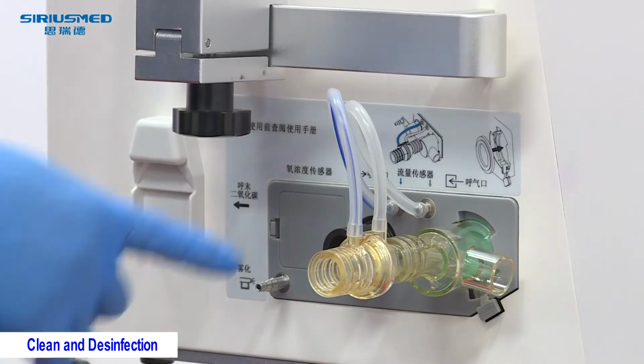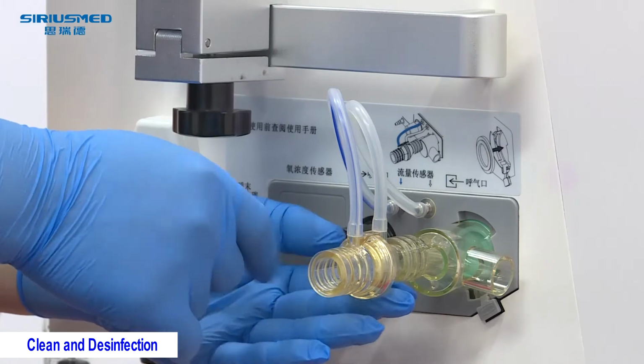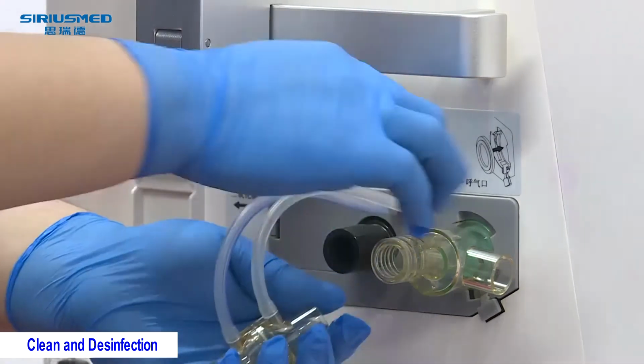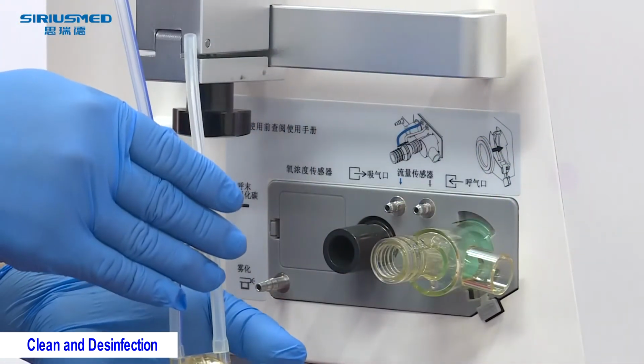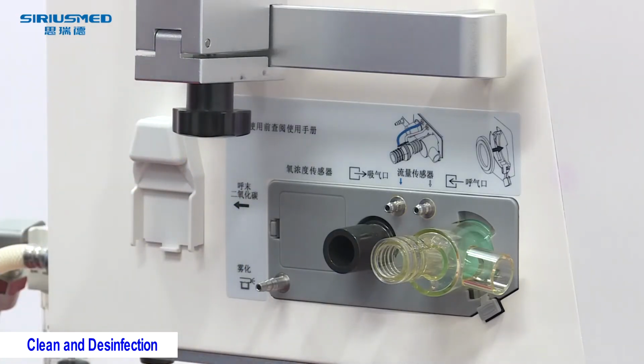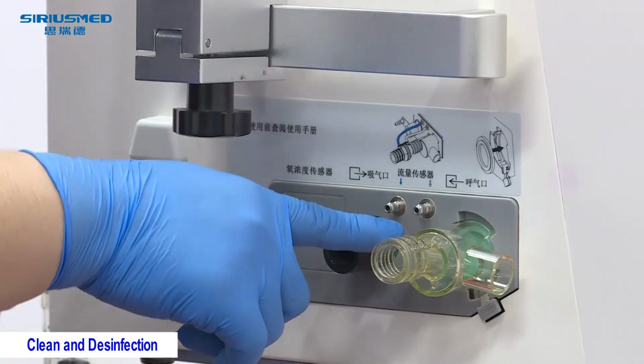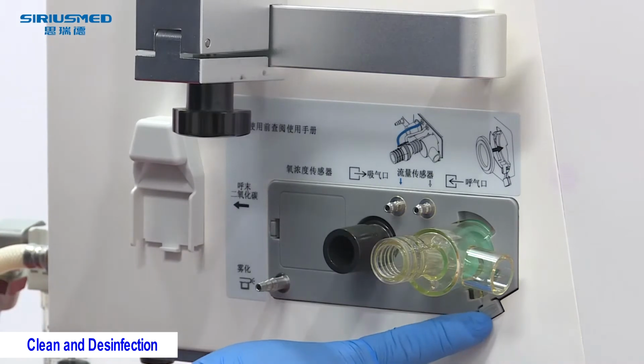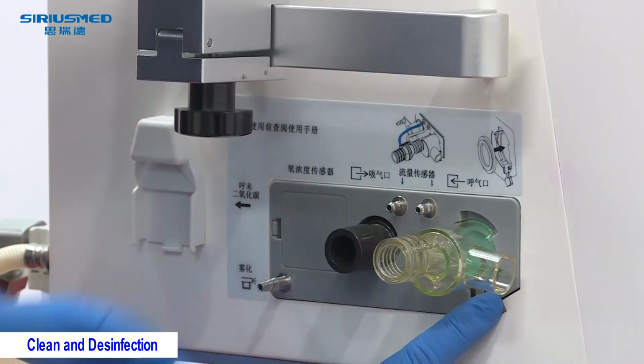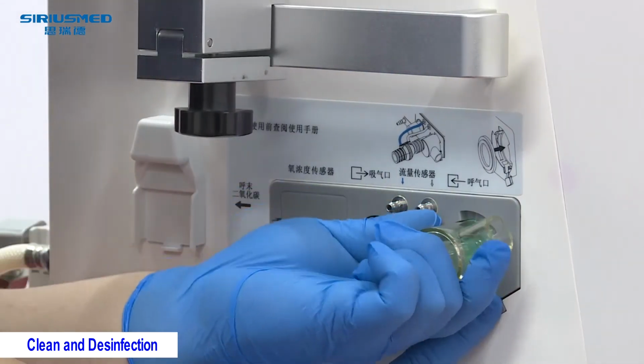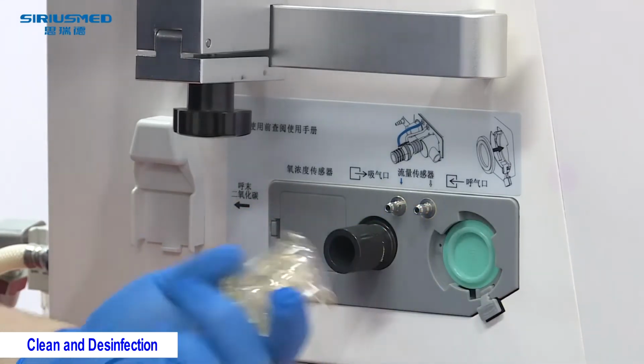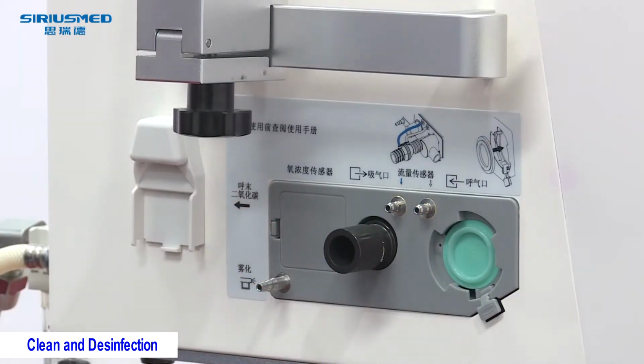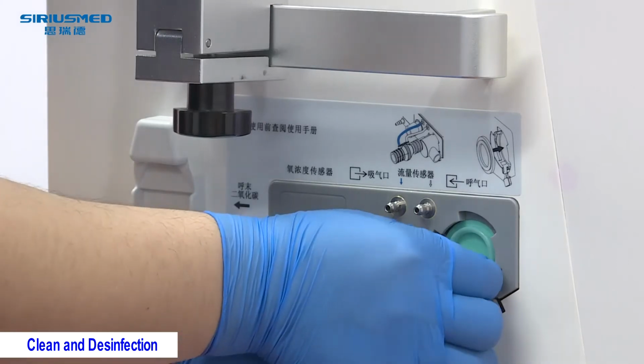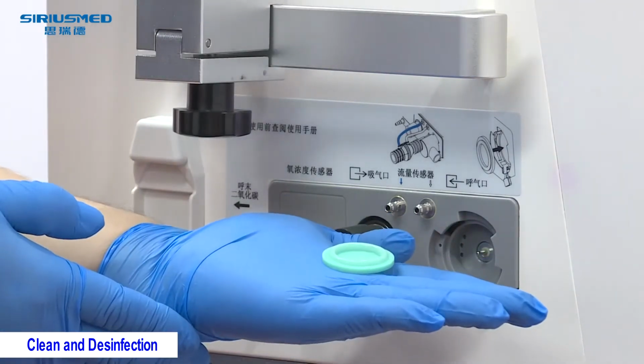Exhalation valve. In this part, we need to take off the flow sensor probe first, and then take off the valve. First, press this button and turn the PEEP valve upright and take it off. And then pick this diaphragm off.